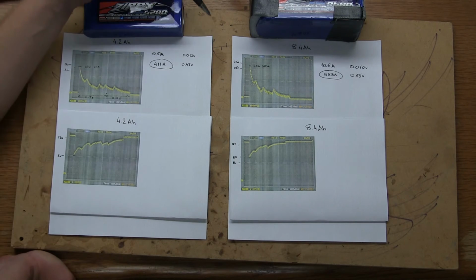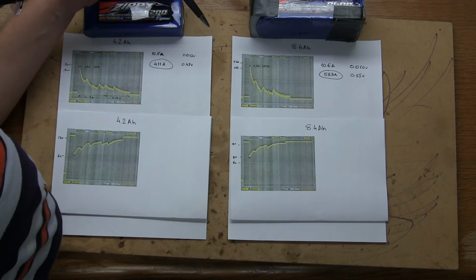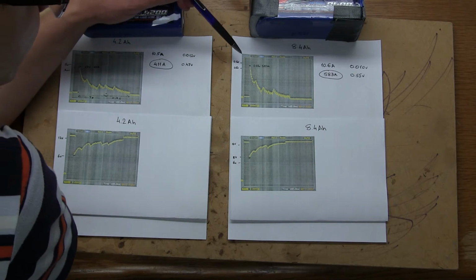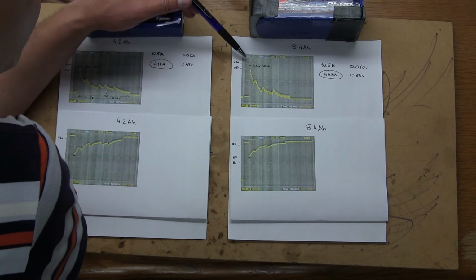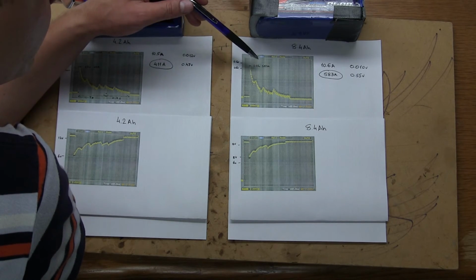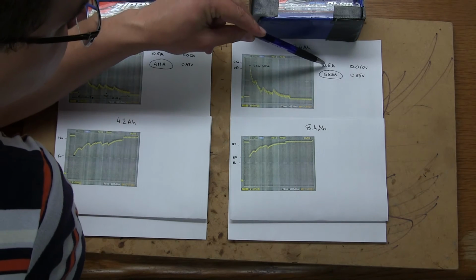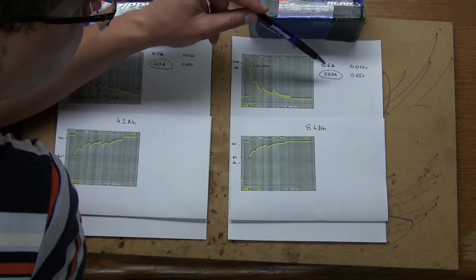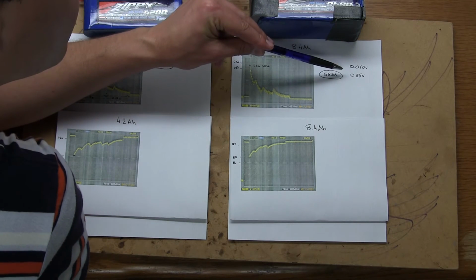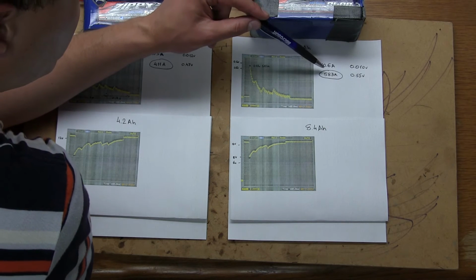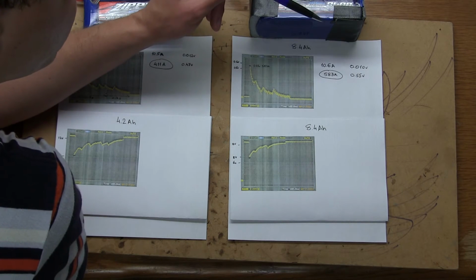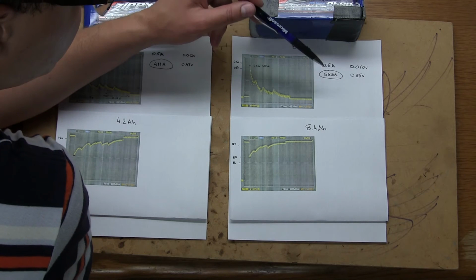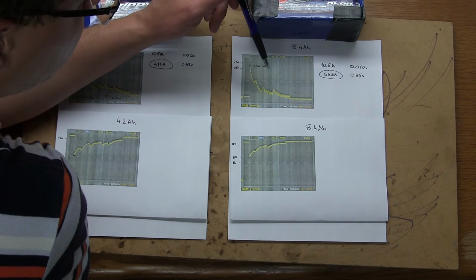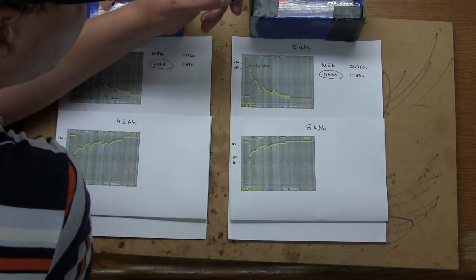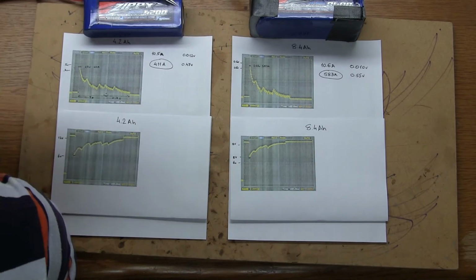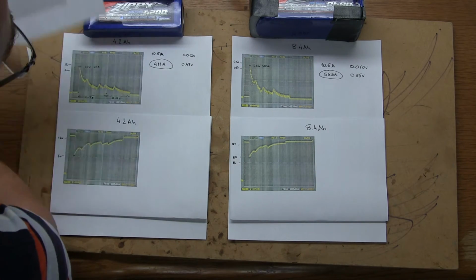If we look at the larger battery, we see a quite different picture. The peak voltage drop is 0.55 volts, and our measurement is that 10.6 amps is 10 millivolts. We see a voltage drop of 0.55 at tops, which corresponds to 583 amps. That's a lot — I don't know if it's a fluke, but it's much more than the battery was designed for.